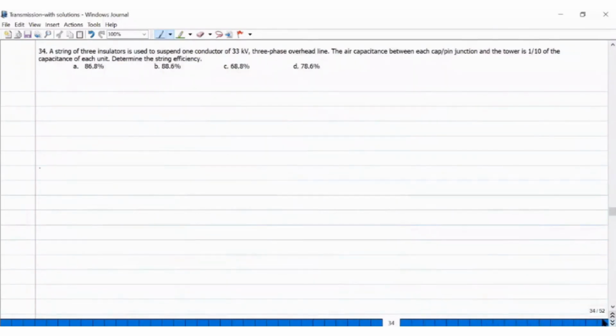Okay, next, 34. A string of 3 insulators is used to suspend one conductor of a 33 kV 3-phase overhead line. The air capacitance between each cap or pin junction and the tower is 1/10 of the capacitance of each unit. So, determine the string efficiency.